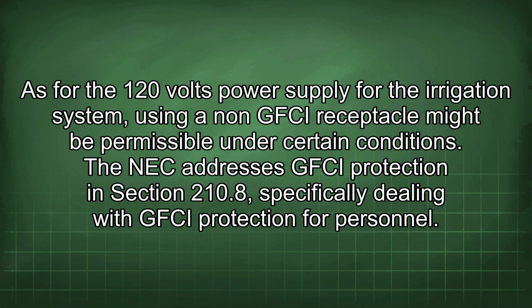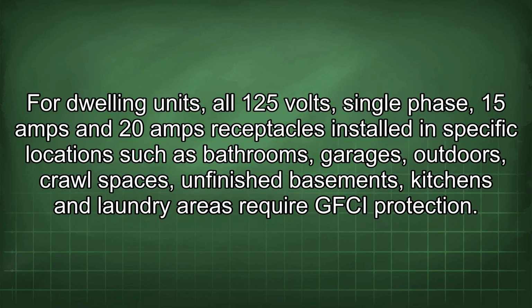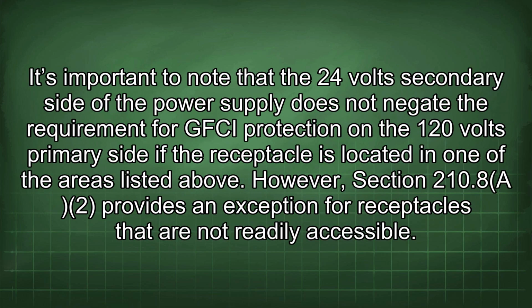conditions. The NEC addresses GFCI protection in section 210.8, specifically dealing with GFCI protection for personnel. For dwelling units, all 125 volts, single phase, 15 amps and 20 amps receptacles installed in specific locations such as bathrooms, garages, outdoors, crawl spaces, unfinished basements, kitchens and laundry areas require GFCI protection. It's important to note that the 24-volt secondary side of the power supply does not negate the requirement for GFCI protection in the 120 volts primary side if the receptacle is located in one of the areas listed above.